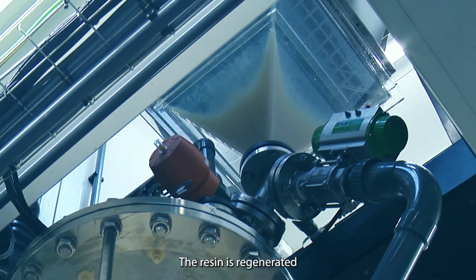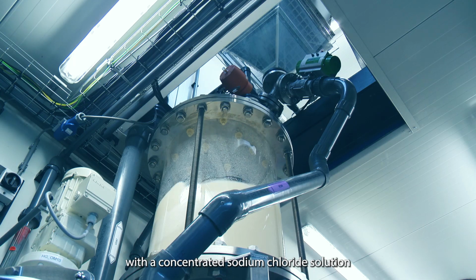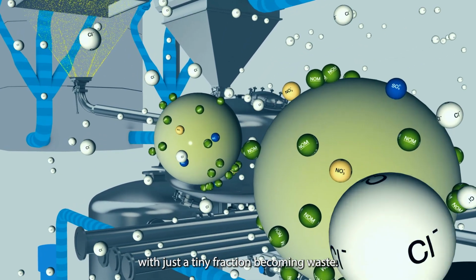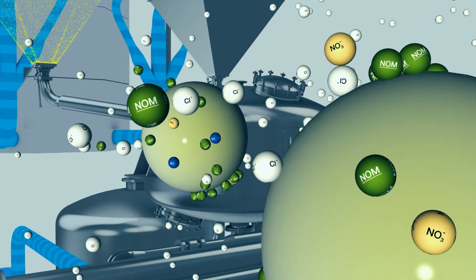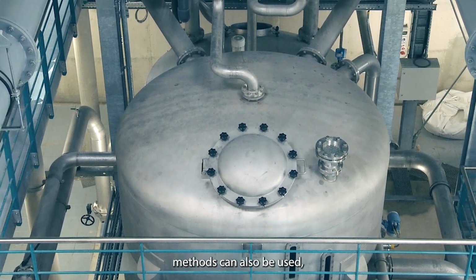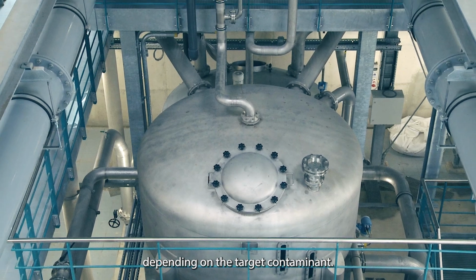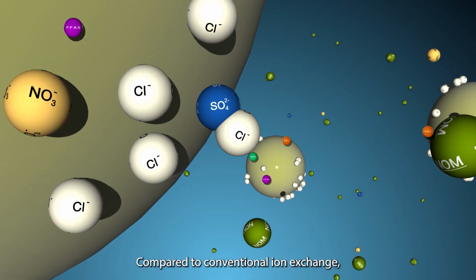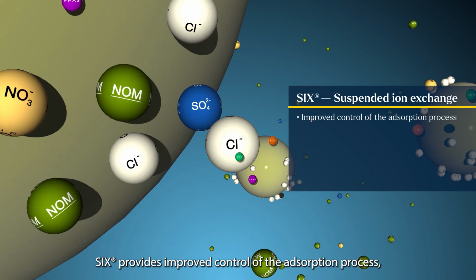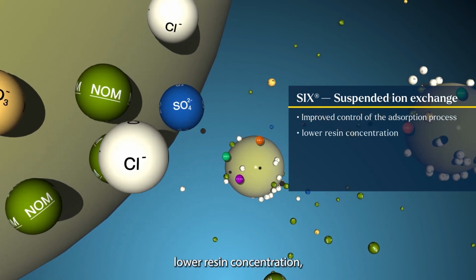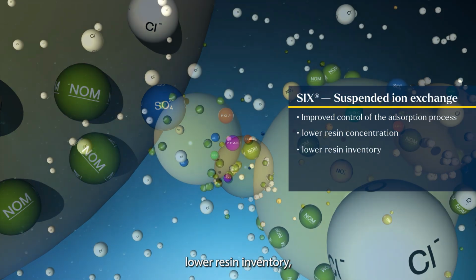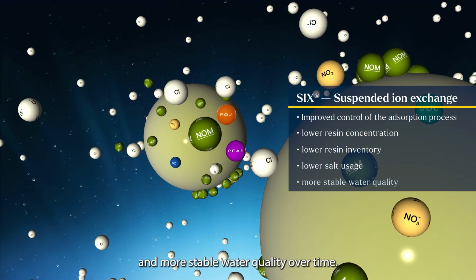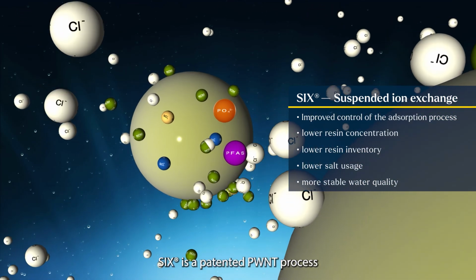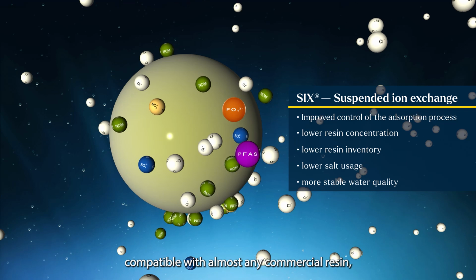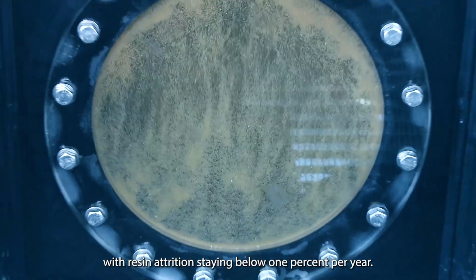The resin is regenerated with a concentrated sodium chloride solution, most of which is recovered and reused, with just a tiny fraction becoming waste. Other resins and regeneration methods can also be used, depending on the target contaminant. Compared to conventional ion exchange, SIX provides improved control of the adsorption process, lower resin concentration, lower resin inventory, lower salt usage, and more stable water quality over time. SIX is a patented PWNT process compatible with almost any commercial resin, with resin attrition staying below 1% per year.